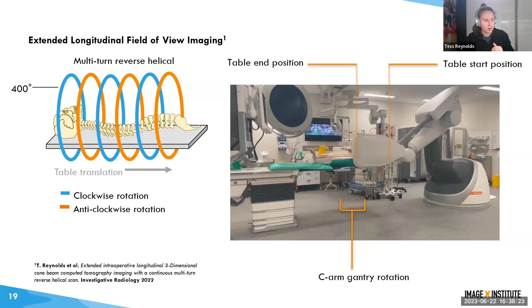If we can sync these rotations, forward and backwards, with a table translation, we can start to image the whole way down the patient table. I won't play this whole video, because it is a bit slow. What we can see here is that we have a pig cadaver on the table, and we're going to try and image this entire spine. As the C-arm is doing its rotation, you can start to see that the table has started translating away from its original position. As we reach the end of that first rotation, we're going to reposition, and then rotate the other way and continue that table translation. All throughout this, we're acquiring our images, and then when we reconstruct, we're going to have a nice single volume that covers the entire length of our required surgical field.